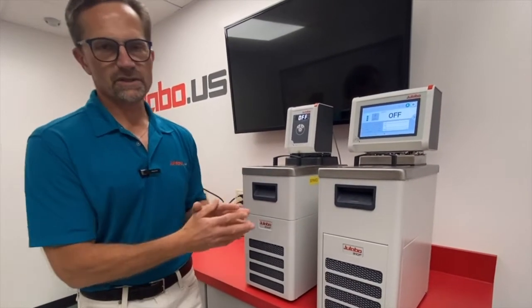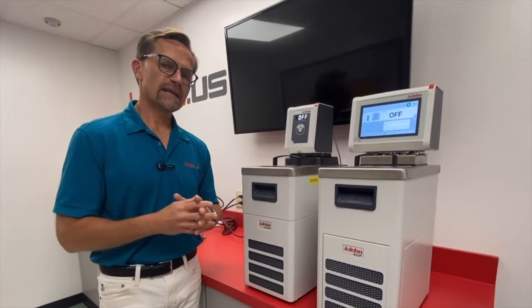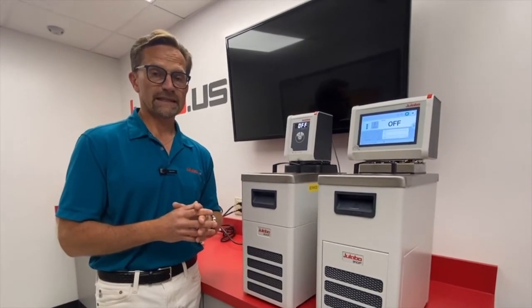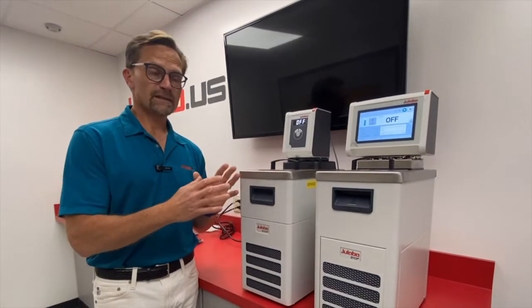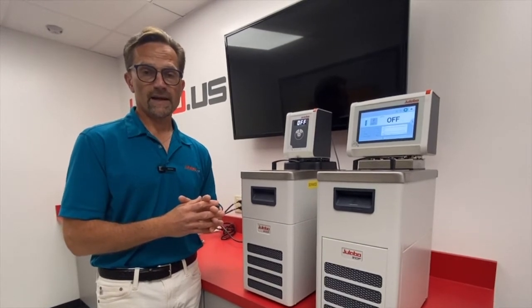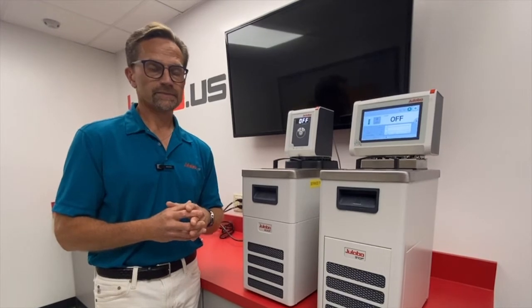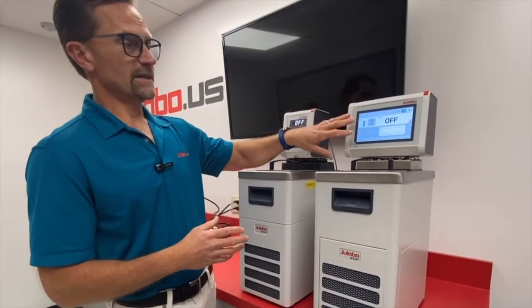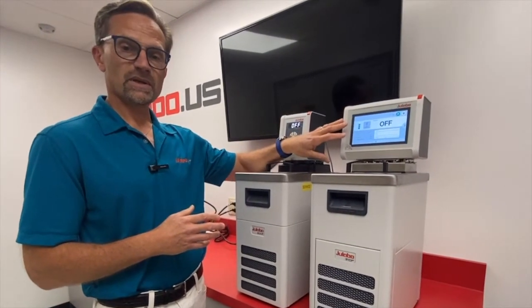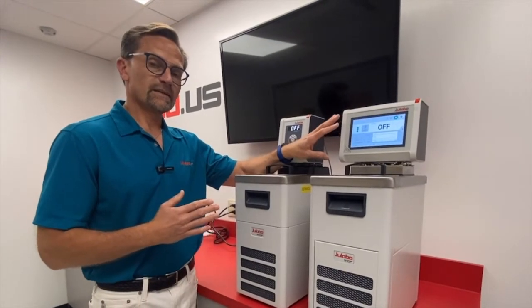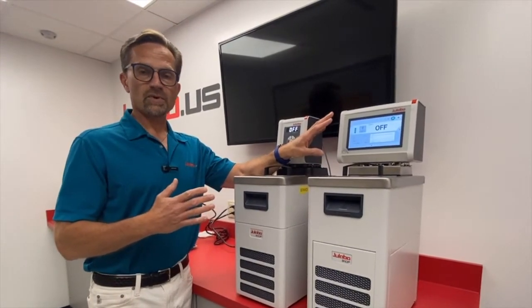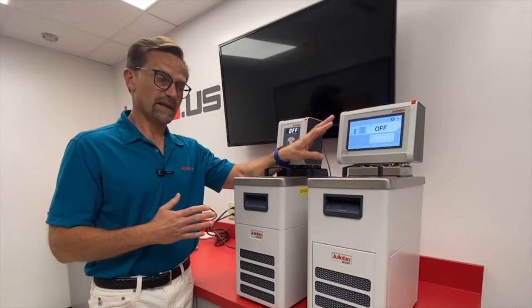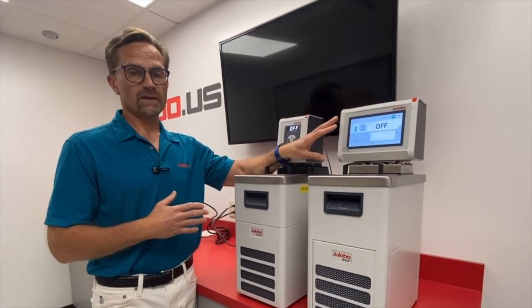Comparatively, the MAGIO systems have a Tmax in heating circulators of 300 degrees C. The MAGIO MS can come with either a 1 or 2 kilowatt heater, and the MAGIO MX has a 3 kilowatt heater. The MAGIO MX has an integrated pressure suction pump with adjustable flow rate up to 31 liters per minute and 13.3 psi. So you have a lot more flexibility with the MAGIO pump.